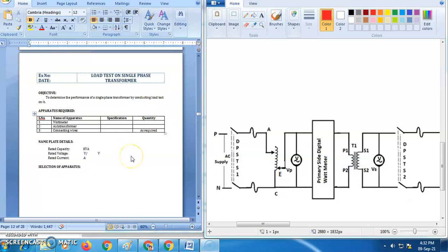So once you enter into the laboratory, you need to go for the table number 27, where you have the apparatuses required for this particular testing, and in that table you can read the nameplate details of the particular transformer which you are going to do the test on, right? You need to record the kVA rating and primary voltage, secondary voltage. Out of these two data you can calculate the rated current.